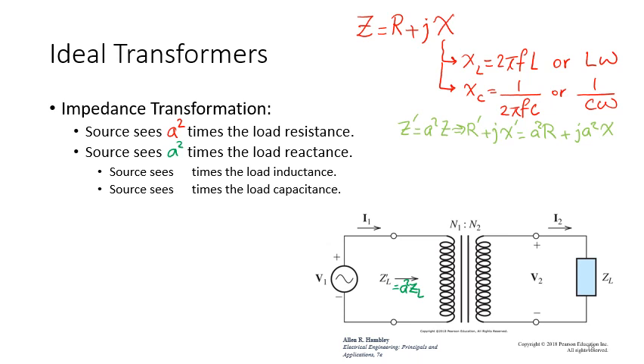For inductances, that relationship is linear, also A squared times, but for capacitance it's 1 over A squared. This is because XC has a reverse relationship with the reactance. So if you want to bring the capacitor from one side of the transformer to the other side, if you want to reflect it, take more care. It's a bit different with resistance and inductance. That's the whole point I want to make here.